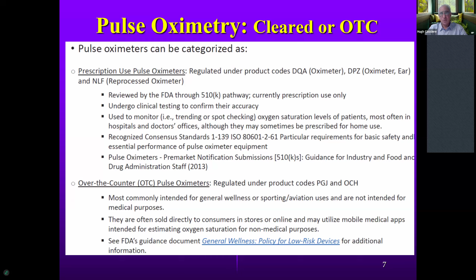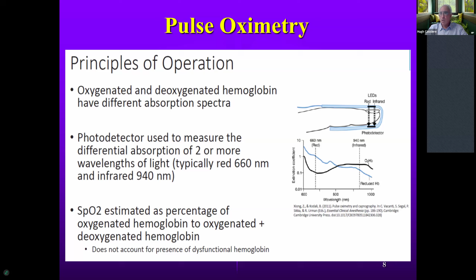Well, how does the pulse ox work? It's actually a simple device physics-wise, right? You guys know you put a probe on the finger, you shine light that's emitted by an LED, and then there's a photodetector on the other side of the finger that picks up the light. There are two different light frequencies that are used in all pulse oximeters on the market. It's the 660 or the red spectrum and the 940 or the near infrared spectrum. And what this light does is it's a differential absorption of the light across the fingertip, and deoxygenated and oxygenated blood have different absorptions of wavelengths. And what do I mean by that? The 660 nanometer light frequency is attuned to the deoxygenated blood. It likes to look for the deoxygenated blood. The 940 is in tune for the oxygenated blood.